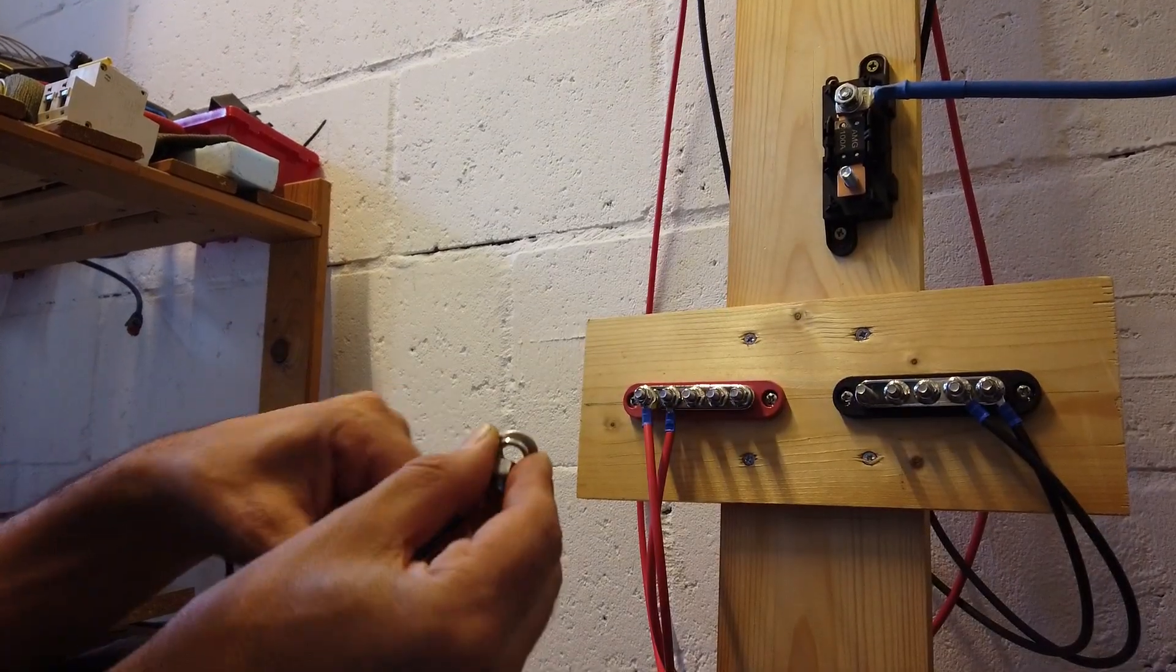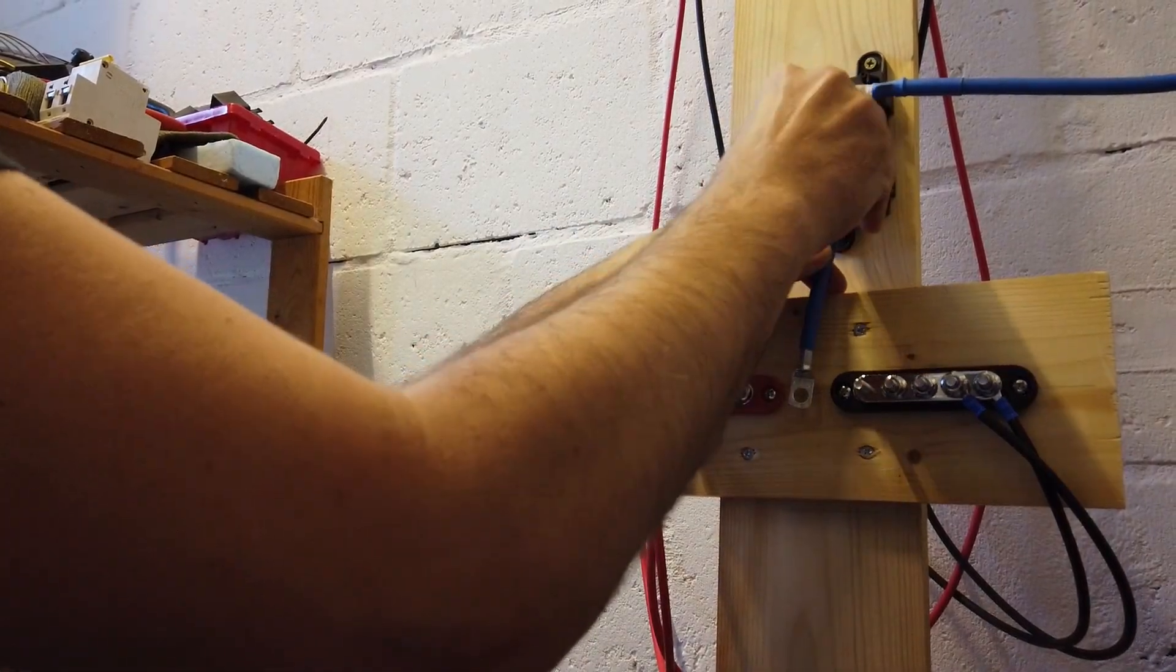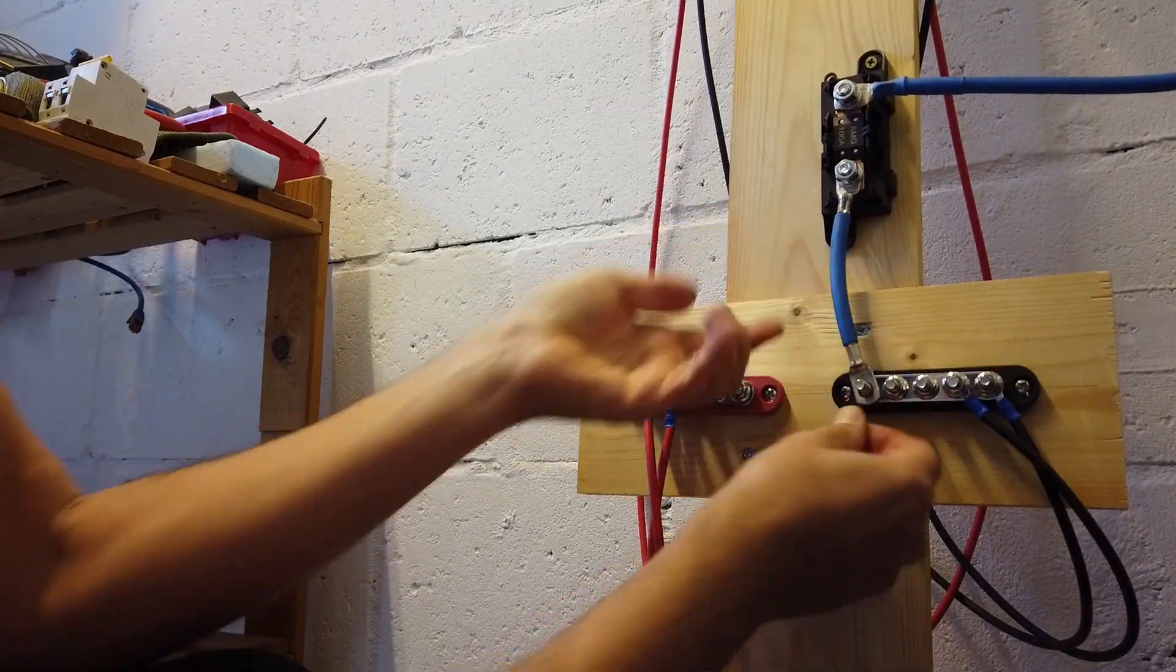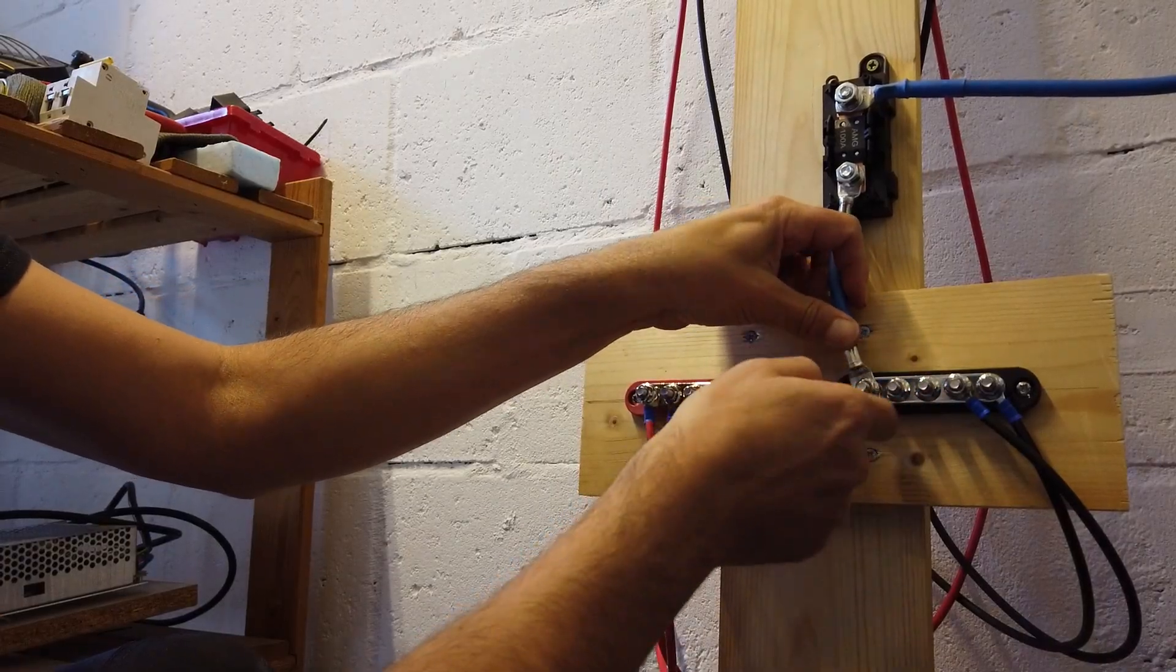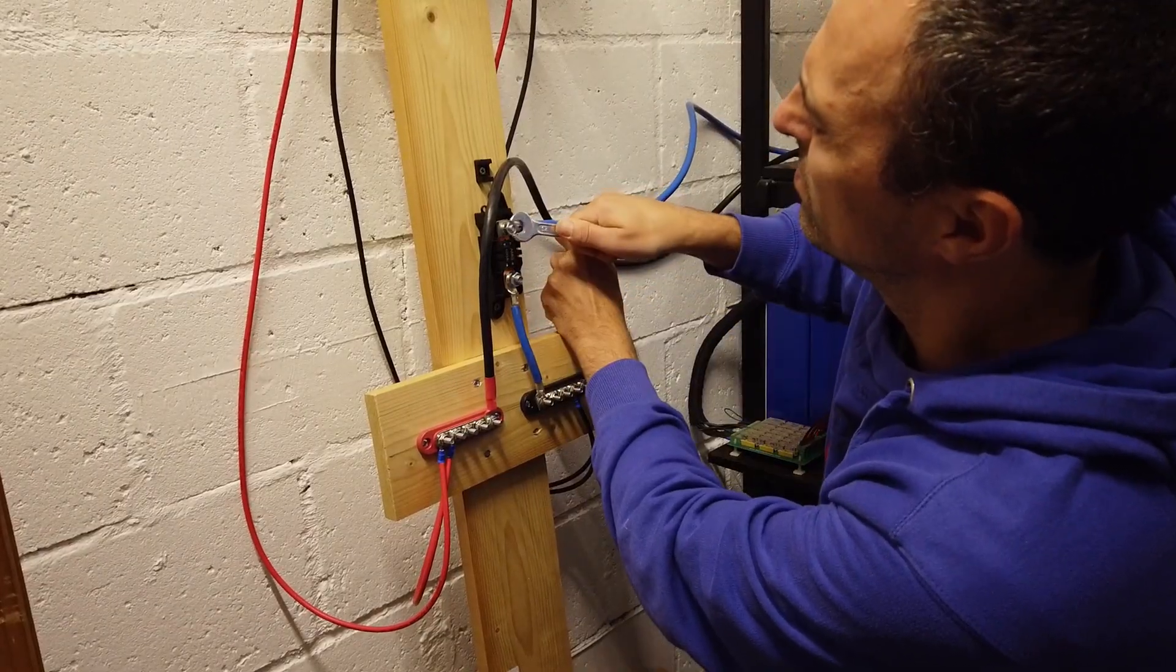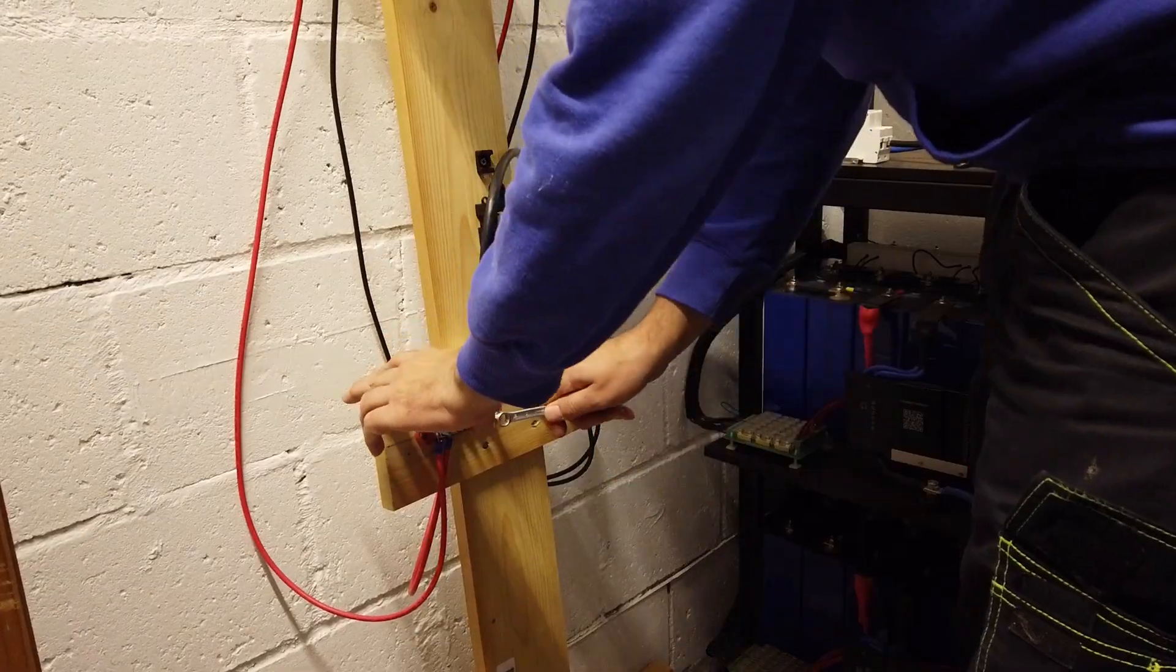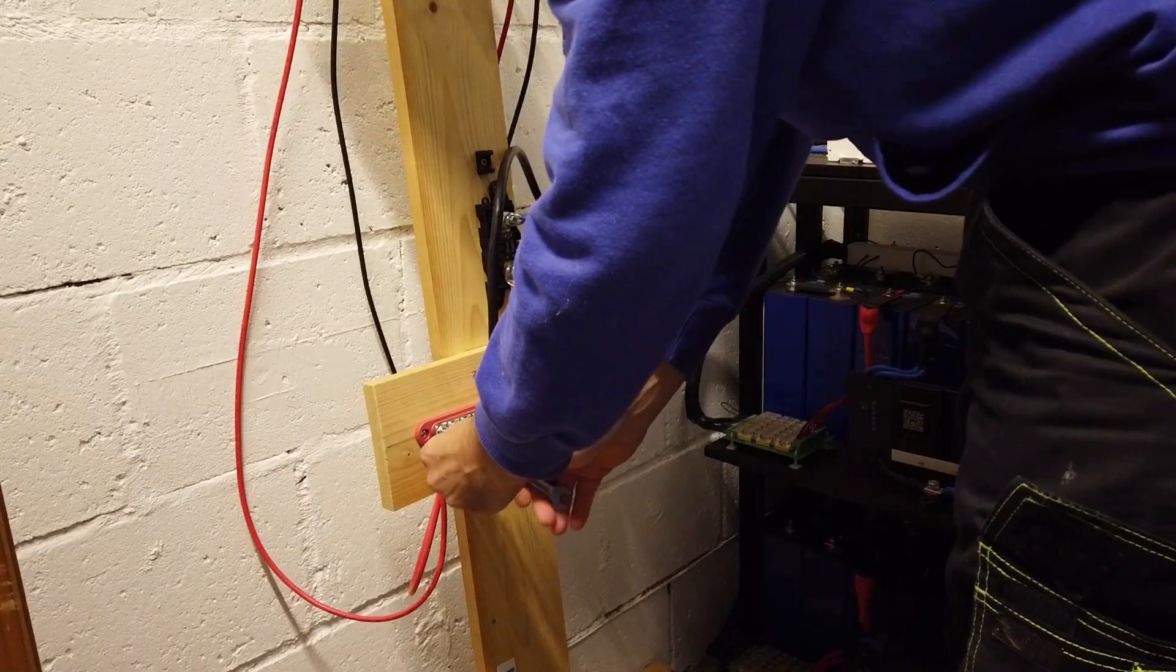No rocket science in the next steps. First, I'm connecting the DC ground via the ANL fuse to the negative DC busbar. The other side of the ANL fuse goes to the negative busbar of the battery. Once done, the positive cable is next in line. Offline, I mounted the DC breaker that acts as a switch on a DIN rail. As a final step, I tighten all nuts and perform a final check on all connections.